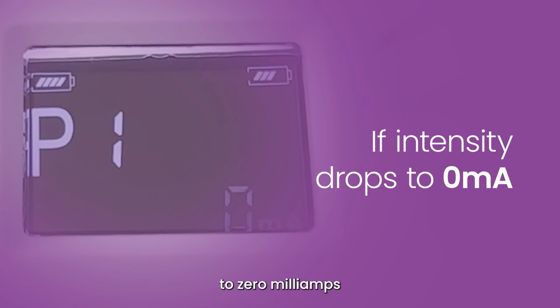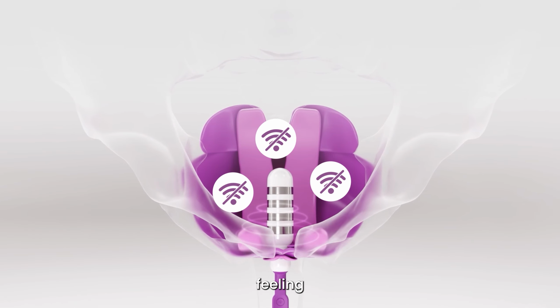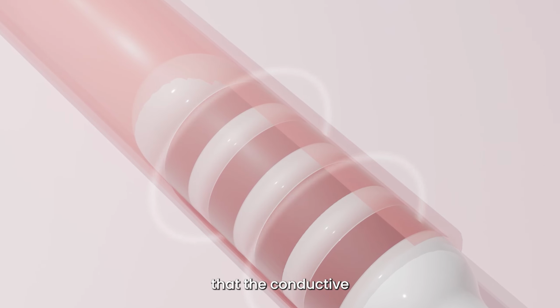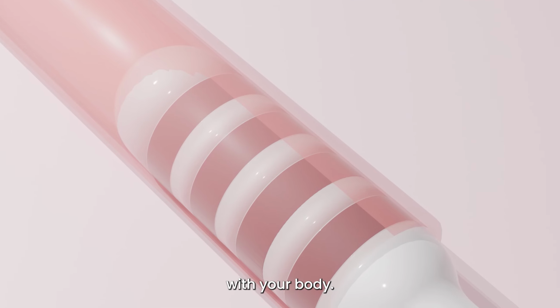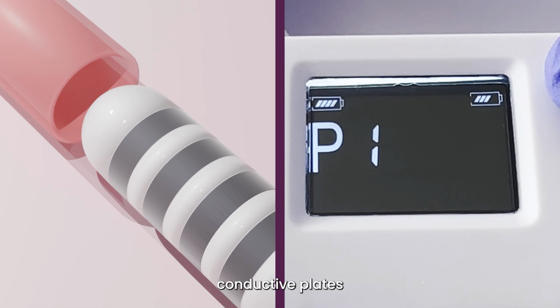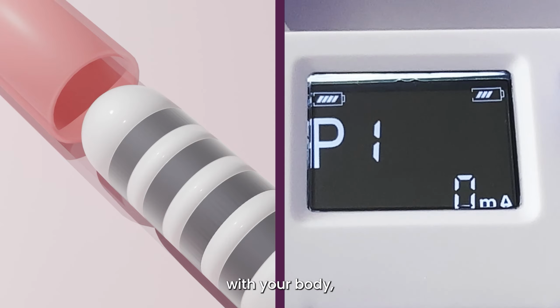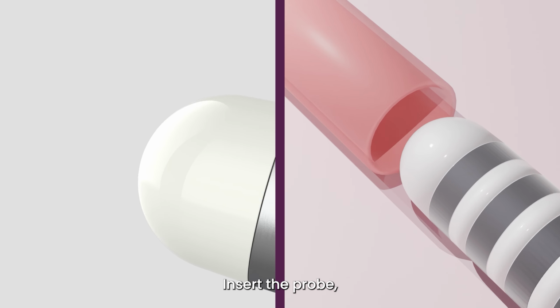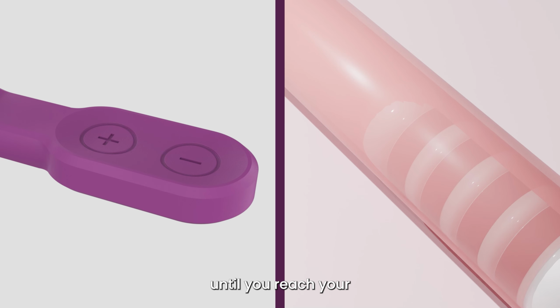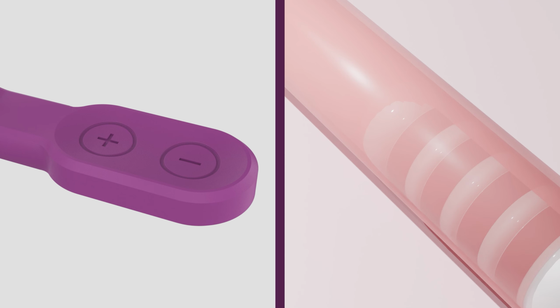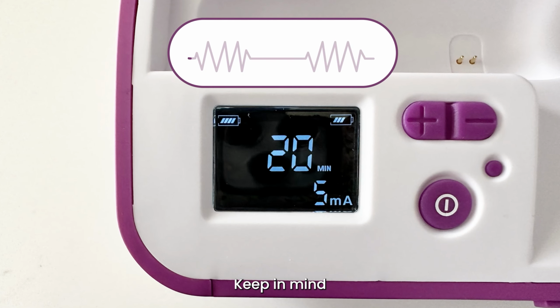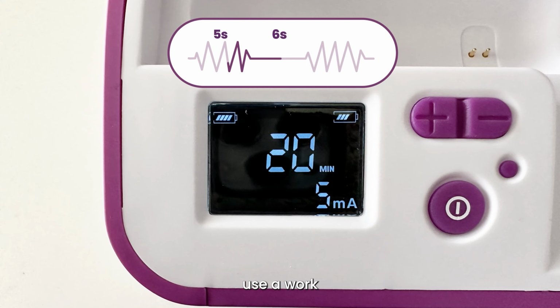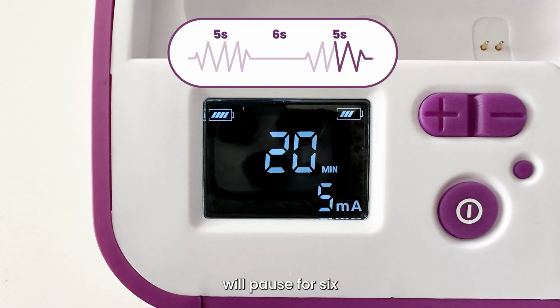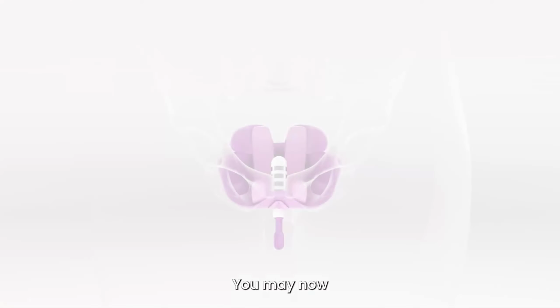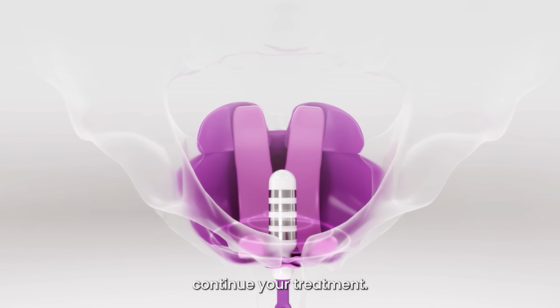If the intensity drops to 0 mA and you are no longer feeling the stimulus, ensure that the conductive plates of the probe are in full contact with your body. Once the probe's conductive plates are no longer fully in contact with your body, the intensity will automatically drop to 0 mA. Insert the probe, then press the plus button until you reach your desired intensity. Keep in mind that presets 1, 3 and 4 use a work and rest cycle where the stimulus will pause for 6 or 10 seconds. You may now continue your treatment.